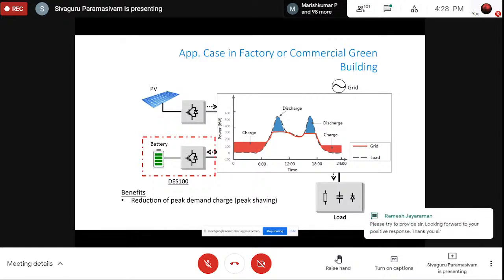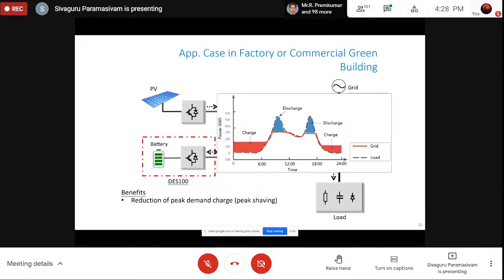So we don't want to waste that, so we can charge the batteries, and we can use the batteries to discharge it to the same load in a different time zone. So this application we call peak shifting or energy shifting. It is nothing but shifting the energy from one point of time and using it at another point of time.